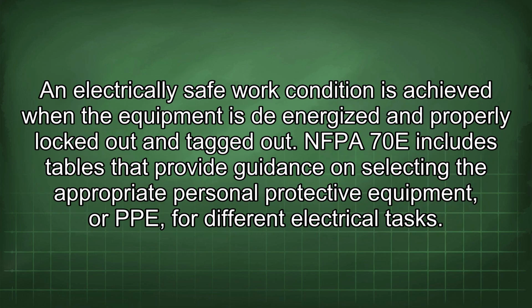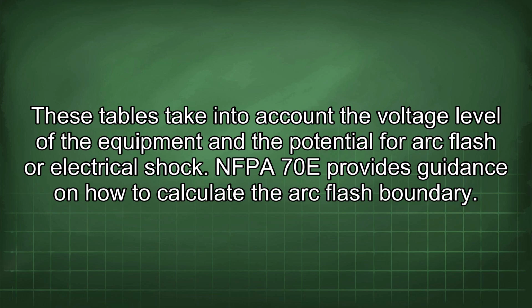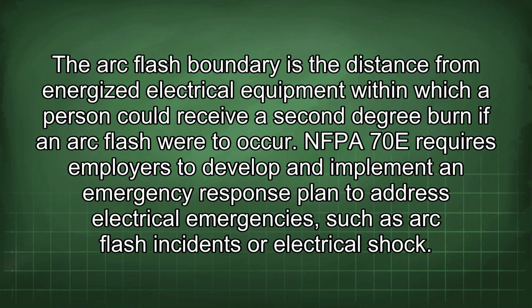An electrically safe work condition is achieved when the equipment is de-energized and properly locked out and tagged out. NFPA 70E includes tables that provide guidance on selecting the appropriate personal protective equipment, or PPE, for different electrical tasks. These tables take into account the voltage level of the equipment and the potential for arc flash or electrical shock. NFPA 70E provides guidance on how to calculate the arc flash boundary. The arc flash boundary is the distance from energized electrical equipment within which a person could receive a second-degree burn if an arc flash were to occur.